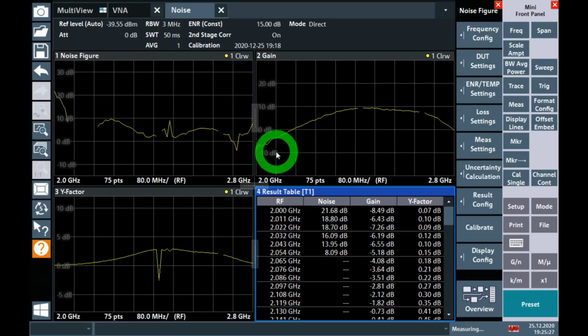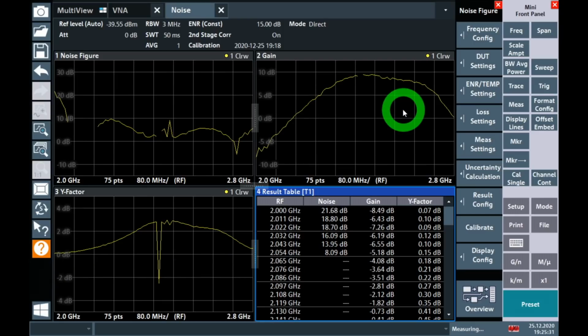Now, if you look at this, you can see that the gain that this instrument is reporting is very close to the S parameter gain. That's not surprising. It has to match. But every once in a while, you do get a little bit of these glitches that happen in the noise figure. So let's see if it happens here one more time as it is sweeping. This time it didn't, but you can see it has some uncertainty. It couldn't do this measurement.